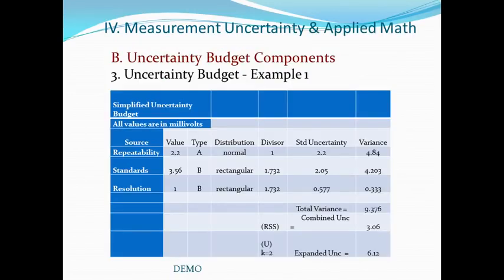Here is an example of an uncertainty budget. It is a very simplified uncertainty budget in that the A's and B's have been listed separately. However, they are all combined in one calculation. To get an idea of what an uncertainty budget looks like, we have several columns. The column on the left is the source of the uncertainty. In this case, we are listing just three different ones: repeatability, standards, and resolution. For each one of those sources, we have an associated value in the next column.